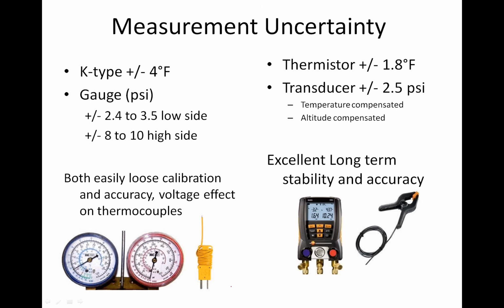And the other thing we can do with a pressure transducer is we can select a lower range pressure transducer. In other words, if our working range is, let's say, 0 to 200, we could actually use a pressure transducer that has that lower working range, and we could expose it to maybe 500 psi and not damage it, because transducers are a lot less susceptible to damage than a Bourdon tube gauge is. So there's some advantages to that. We can select transducers that are closer to our desired measurement span without the fear of damaging. And we can't really do that with a Bourdon tube gauge. If we're going to use that R22 410A gauge, we've got to make sure that the pressure range is high enough to handle the 410A without damaging the mechanics of the gauge.